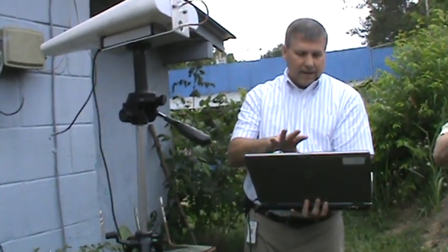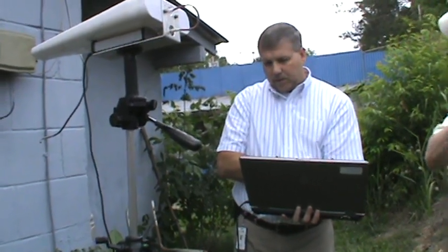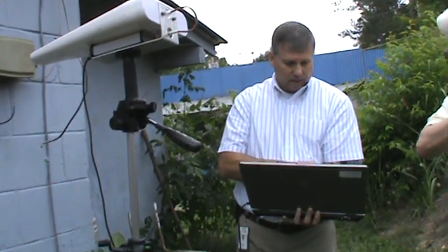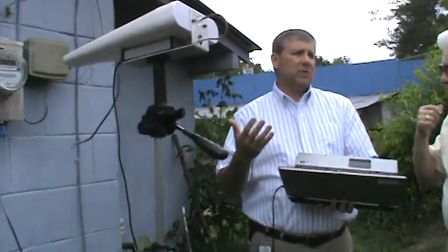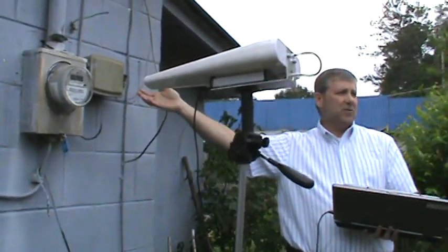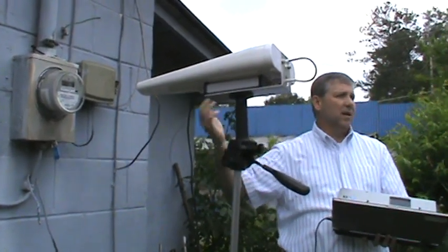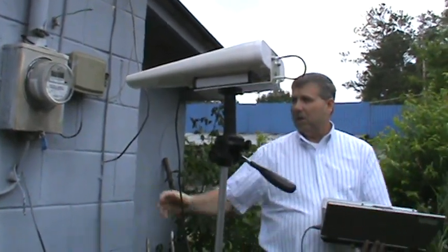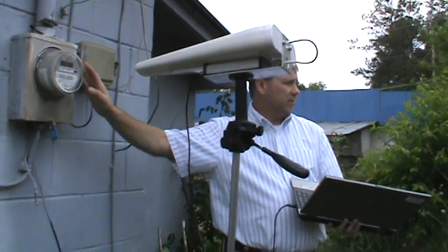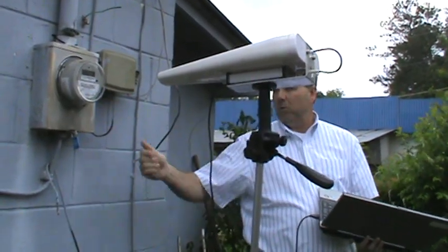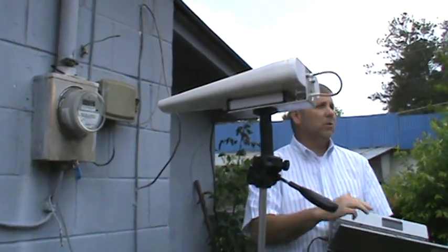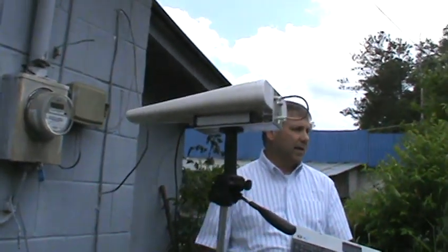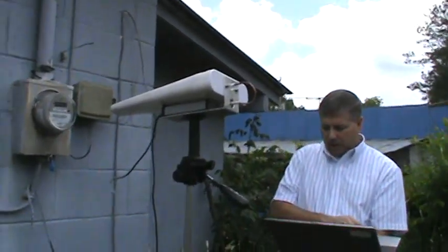And so we take that data, and we enter it into a spreadsheet that we have put together for the customer, for Mr. West in this case. We can also do this with the microwave. We go inside the home and we do it for a lot of customers because a lot of customers are concerned, well, my recliner sits right behind the meter while I watch TV for hours every night. Well, the best way to block RF is to wrap a metal case around it, and all our meters are installed in metal meter bases. So usually when we go inside and measure, it's so low it doesn't even show up on the graph. But we still do it to show the customer that the RF inside the house is low.